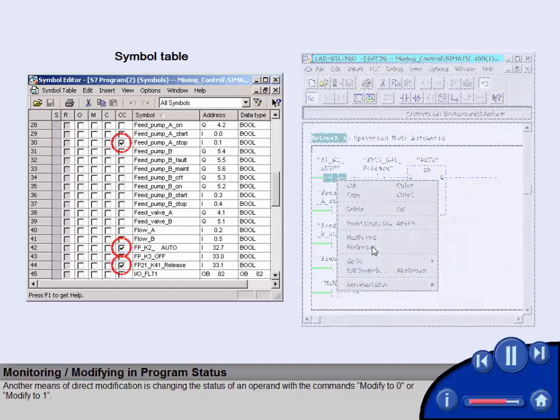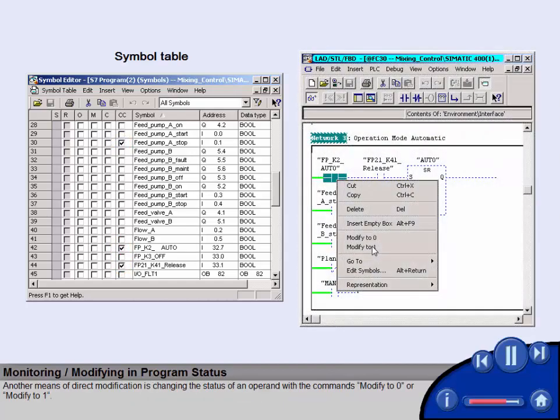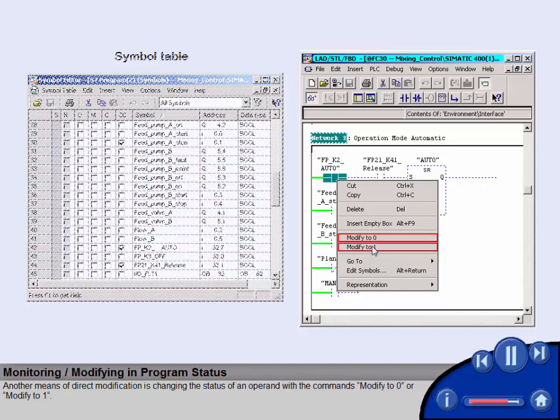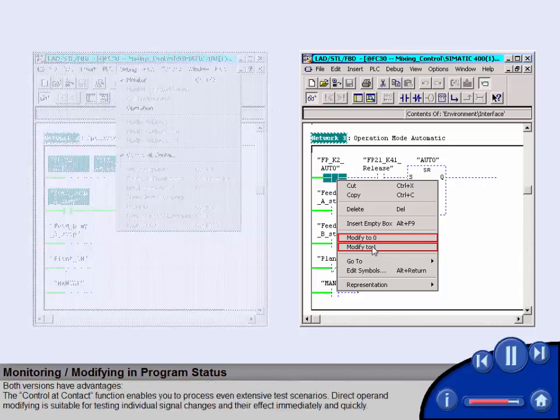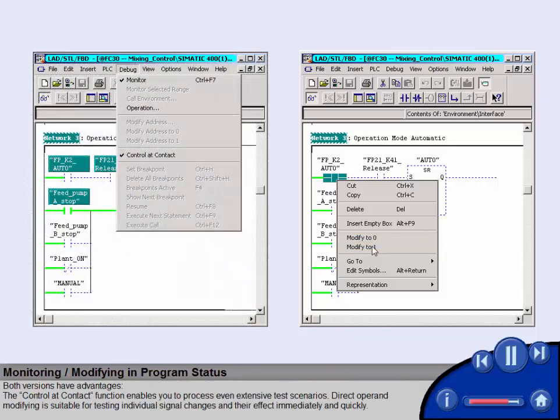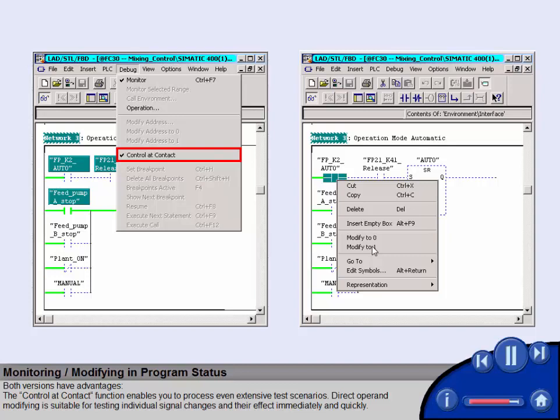Another means of direct modification is changing the status of an operand with the commands modify to 0 or modify to 1. Both versions have advantages. The Control at Contact function enables you to process even extensive test scenarios. Direct operand modifying is suitable for testing individual signal changes and their effect immediately and quickly.